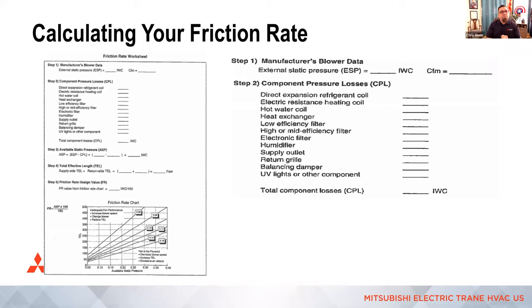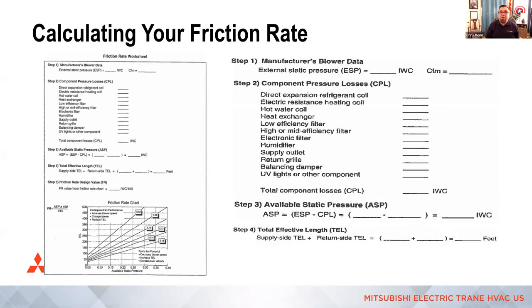All right. Then you'll see we deduct all of those CPL, component pressure losses, from what we started with to end up with what's available, your available static pressure. And if you remember from the previous screen, that's the number that's needed for the top side of your equation. Of course, we add up your supply side total equivalent length and return side total equivalent length for the longest run, not all of them, it's not a stock list, to get the bottom side. And then we do the math. It's actually pretty simple, okay?